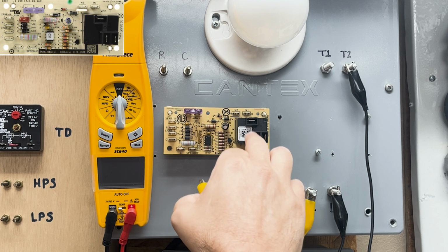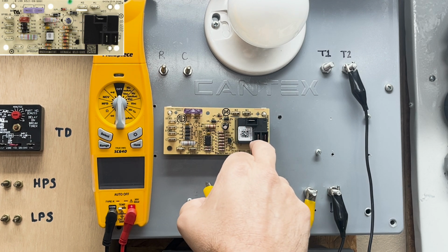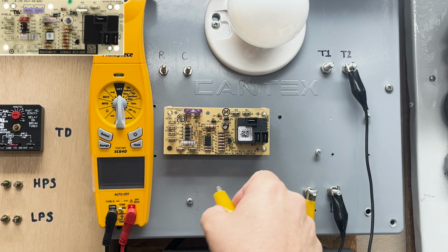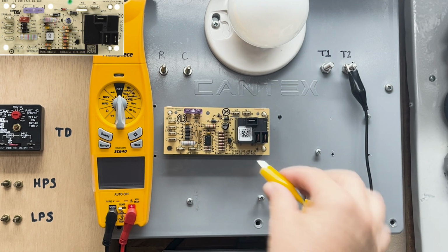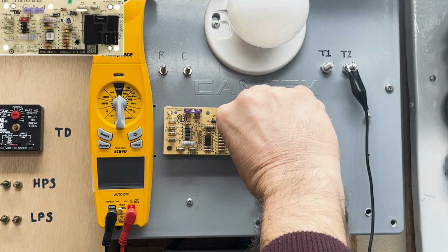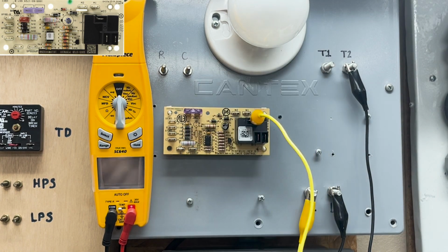Now there's a common terminal, a normally open, and a normally closed terminal. I'm going to go ahead and wire L1, which is line voltage. Line voltage will always go to your common terminal. We're going to come out of the normally open because we don't want the load to run.